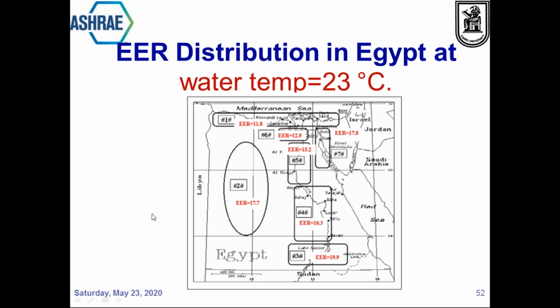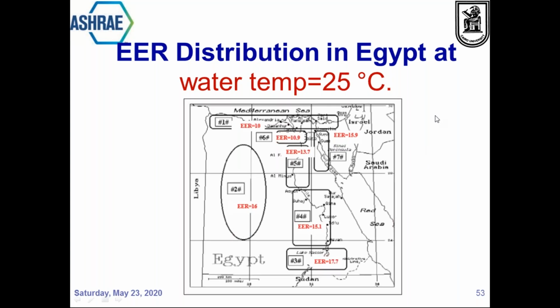So I'm just trying to walk you through the results. I'm not going to bore you with more experimental results, but once you get the test rig calibrated, tuned and running, you expect to get multiple good results that can mean a lot to the designer. Now let us go to 25. At 25, the EER is still higher, but less than at 23 degrees centigrade spray water temperature.